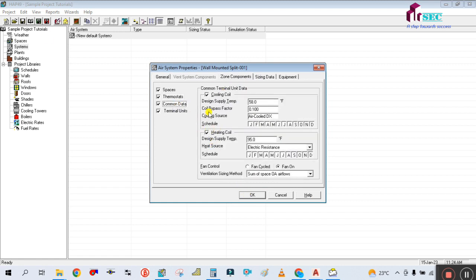In Common Data, we only need cooling, so simply check the Cooling option. The design supply temperature is 56 degrees Fahrenheit, and the coil bypass factor is 0.12. The schedule should be activated for all months - January until December should all be activated.